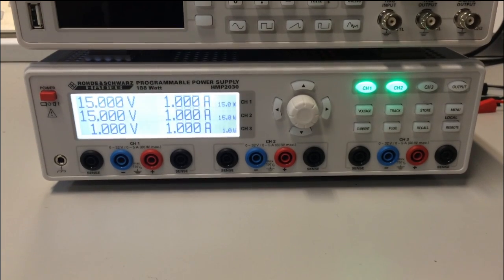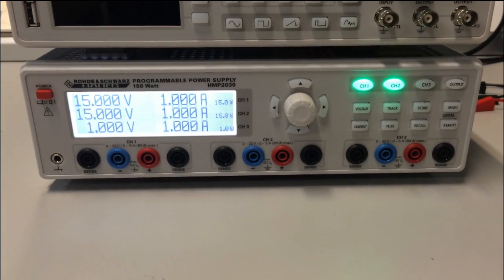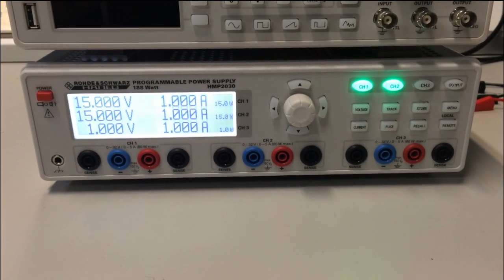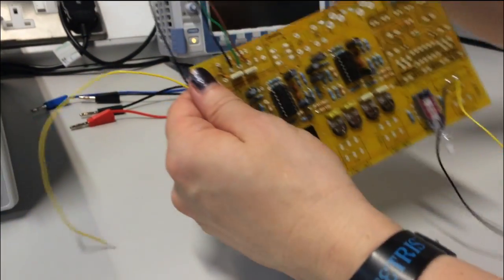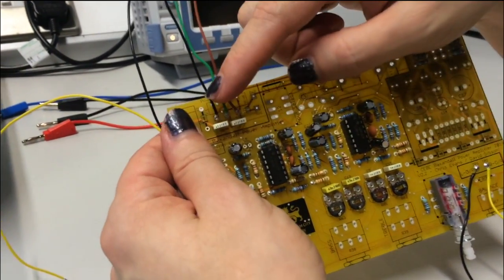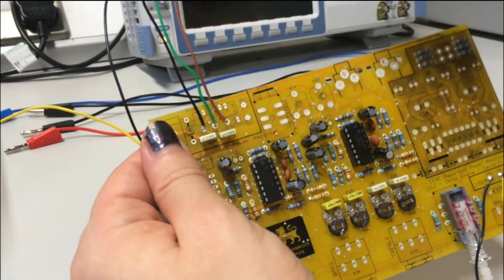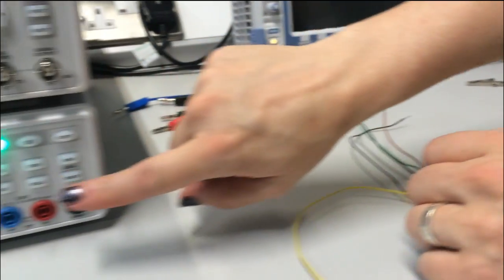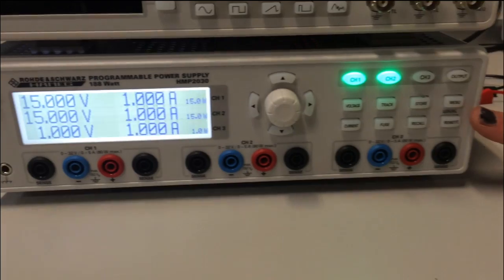Right, now the next stage we need to do is to actually power the board. Now the three leads that you want to be using are these that we've just been using for the resistance testing. So you've got your minus 15 volts, ground and your plus 15 volts. And to do that, we're going to use this box here, which is your power supply.